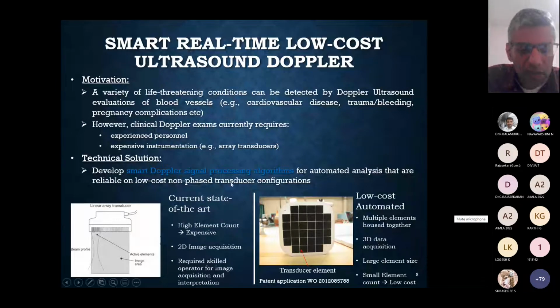So that essentially was the focus of this project, where we developed smart signal processing algorithms that can automatically analyze the Doppler information. Not only that, we also built some specific sensors. As I show in this comparison here, these sensors are non-phased. Instead of using an acoustic array, they use a set of individual sensors, which are all connected together, and they're able to automate the Doppler acquisition.